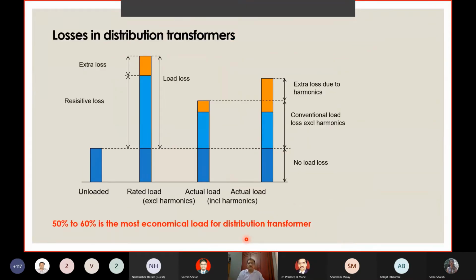Look at the transformer. I have shown you a graph where, at typical 100% rated load, excluding harmonics, the losses are here like this: fixed losses or no-load losses, conventional load losses, and extra losses due to harmonics are also mentioned here. Whereas if you are able to lower the load on the transformer, not the rating of the transformer, your I2R losses or copper losses can come down. These are called iron losses, these are copper losses. These copper losses can come down dramatically.